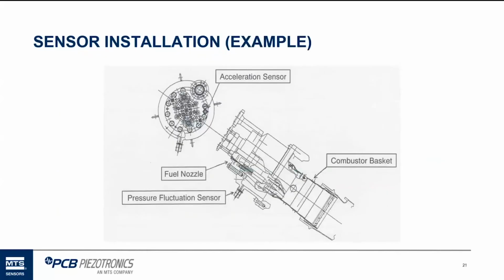Another example of an installation, this is a drawing actually from an OEM, is showing where a vibration sensor is mounted, and then the pressure sensor is mounted usually right by a fuel nozzle in that area on the combustion basket.